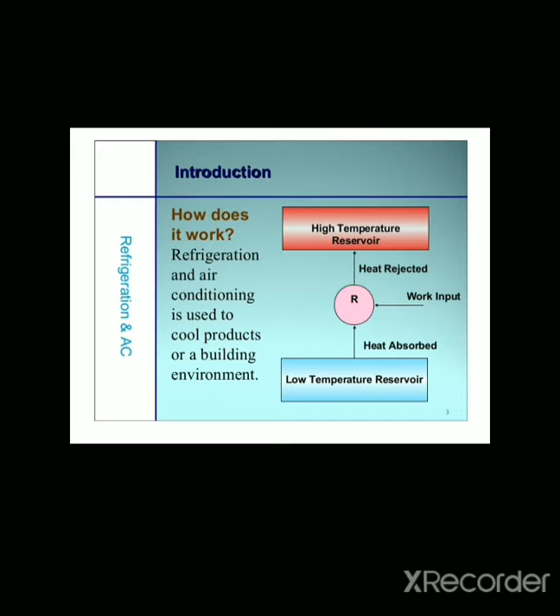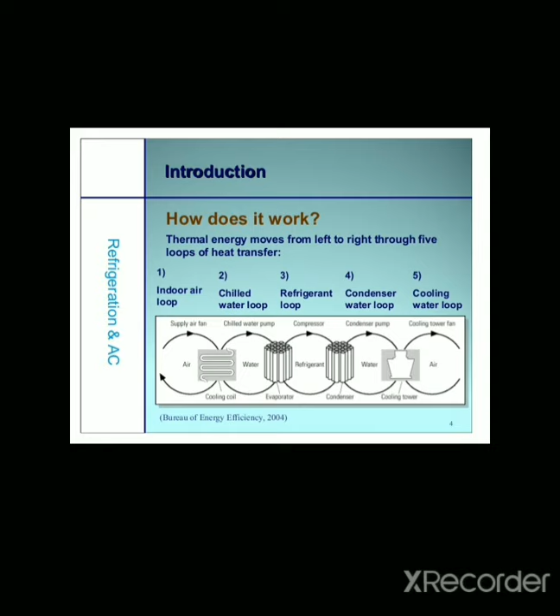Thermal energy moves from left to right through five loops of heat transfer. The first loop is the indoor air loop, the second is the chilled water loop, the third is the refrigeration loop, the fourth is the condenser water loop, and finally the fifth is the cooling water loop. So these are the loops of the heat transfer system, and according to these five steps it is going to work.